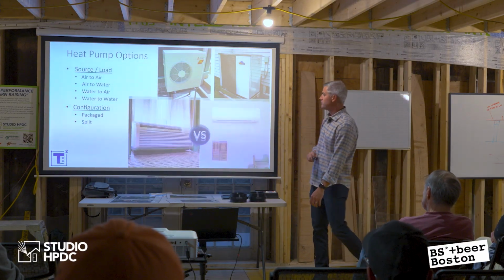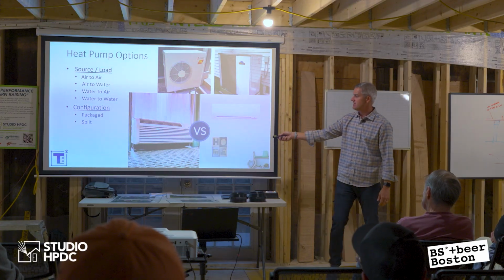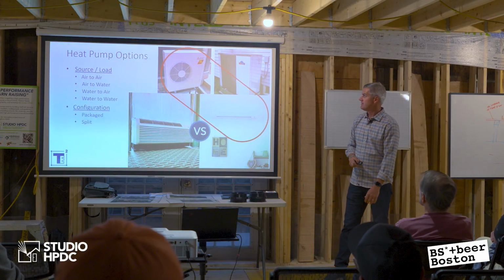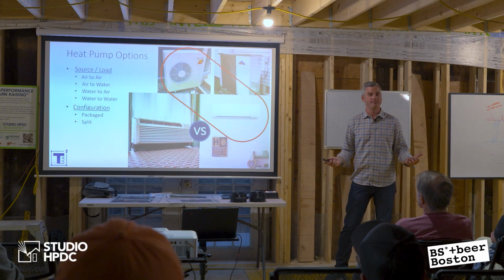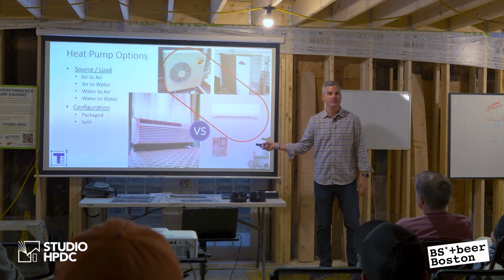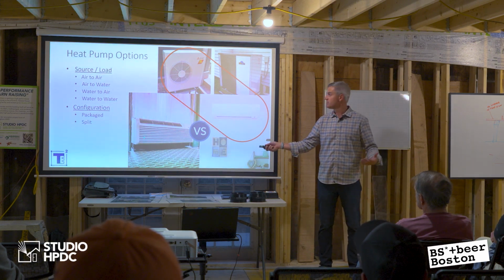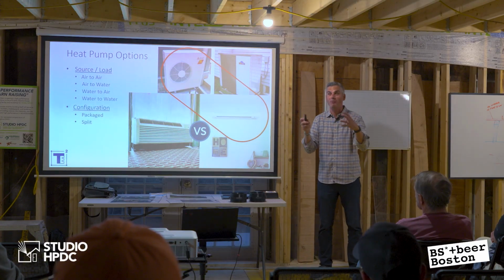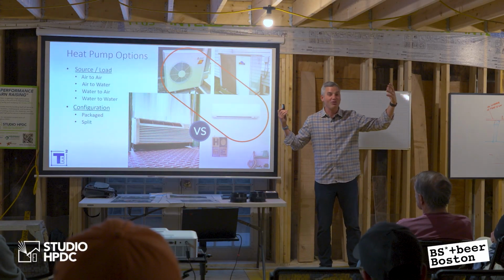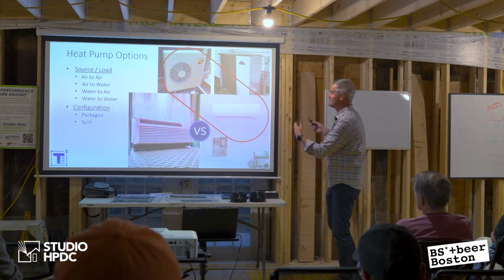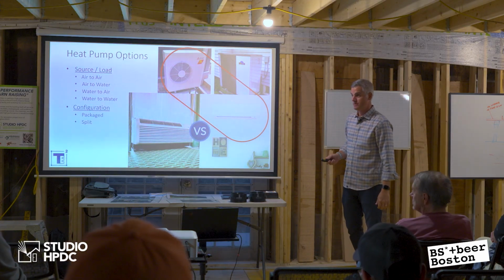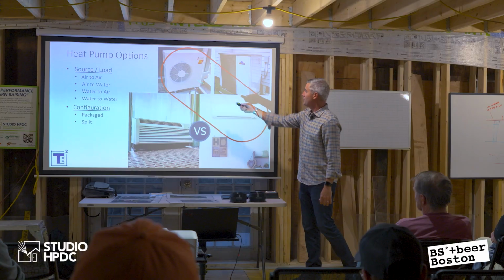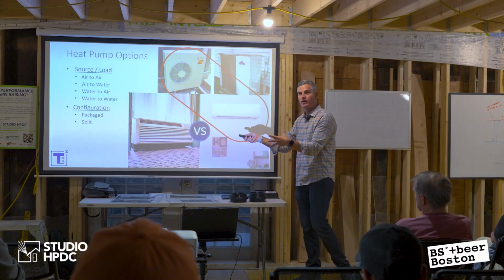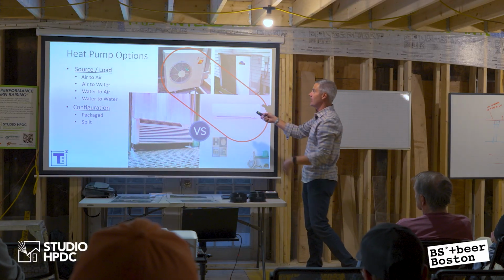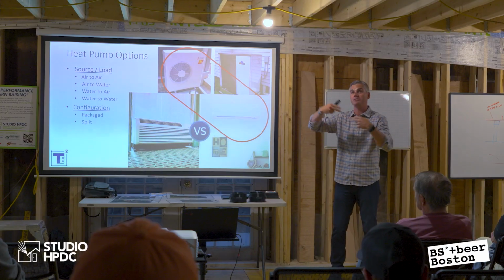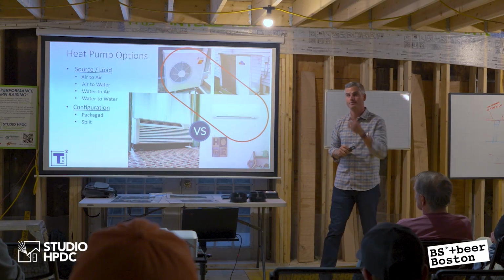I can have a package or split. So what's the difference between this and that? That is a split system. This is a packaged heat pump. Packaged, split, hence mini split. Let's make it small, let's split it apart. Brilliant, right? A packaged unit means both functions of the outdoor unit and the indoor unit are packaged into one box. And then this is a split unit, meaning the outdoor unit and the indoor unit are separated apart and then connected with a set of pipes between the two. They call these ones mini splits.